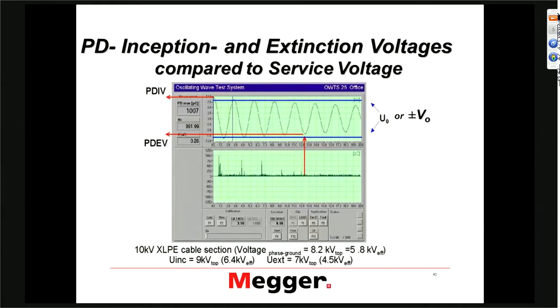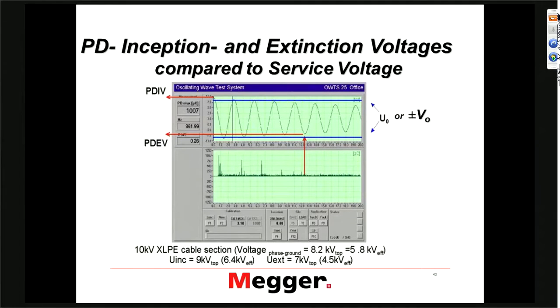Extinction voltage is also very important because partial discharge has what we call a hysteresis behavior. That means the inception voltage and extinction voltage are not identical. As you raise the voltage, you get an inception. As you decrease the voltage from the inception level, it will not extinguish at the same level, but typically at a lower level. What people really look for when they do PD testing is that the extinction level is above operating voltage, because otherwise you have constant PD on your cable.